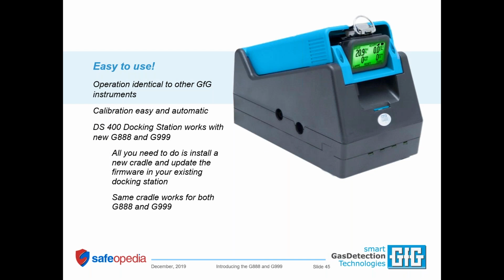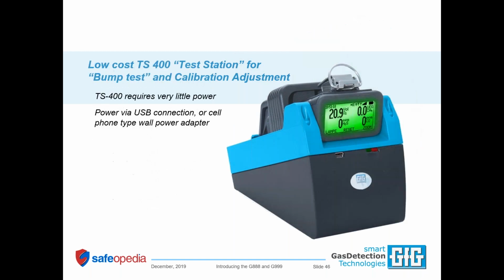That's going to be the accessories that come along with the instrument, including the docking stations. If you want to adapt an existing DS400 or DS404, just make sure you're operating the most current firmware and change out the cradle. For old docks, you might have to send it to the factory for a small hardware update, but most docking stations sold over the last couple of years are ready to go as long as you have the correct cradle and firmware. Any docking station you buy will come equipped with the most current firmware and correct cradle for what you'll be testing, so this is only an issue if you want to modify an existing dock.